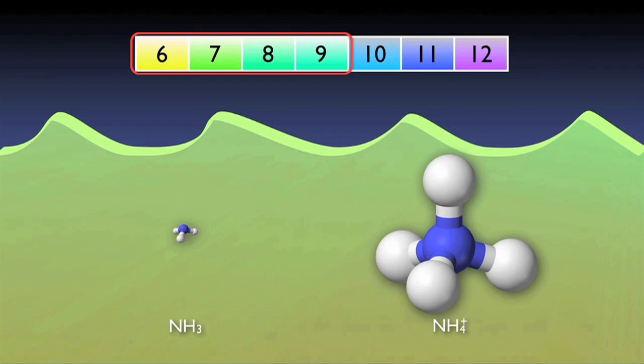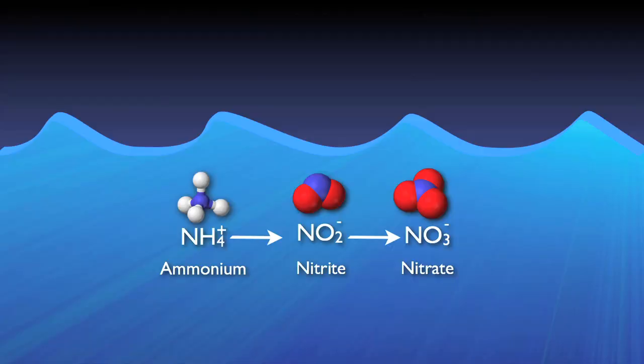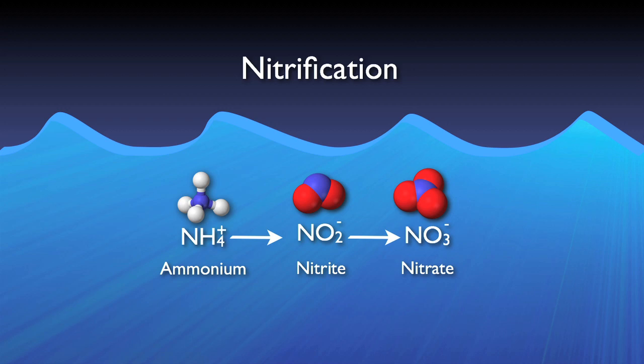Since ammonia testing accounts for both forms — ionic and gaseous — it is not necessary to worry about each form separately. No bacteria is necessary for this conversion; it just happens. The next step in the process consists of converting ammonium to nitrite and then nitrate. This two-step process is usually lumped into one term: nitrification. This step is facilitated by specialized autotrophic bacteria.